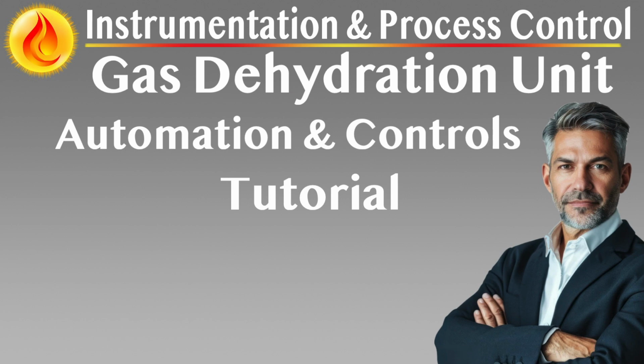The control system interfaces with the Distributed Control System, DCS, or local control panels for autonomous operation and integration into broader plant shutdown and safety systems. The instrumentation infrastructure covers reboiler temperature control, still column vapor handling, rich to lean glycol separation, stripper gas flow if applicable, and flash gas recovery, while supporting diagnostics, redundancy, and safety interlocks. Reboiler temperature and heat source control.